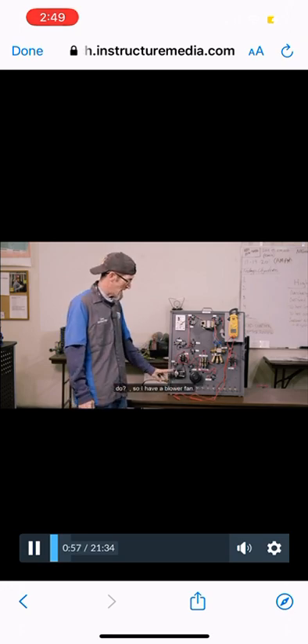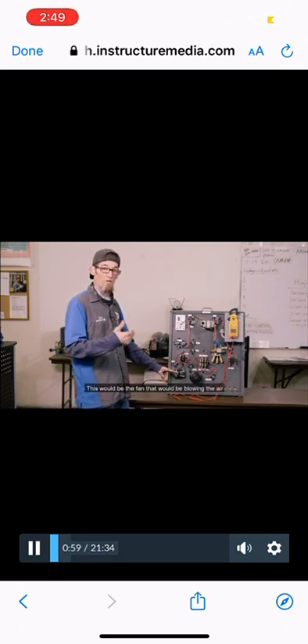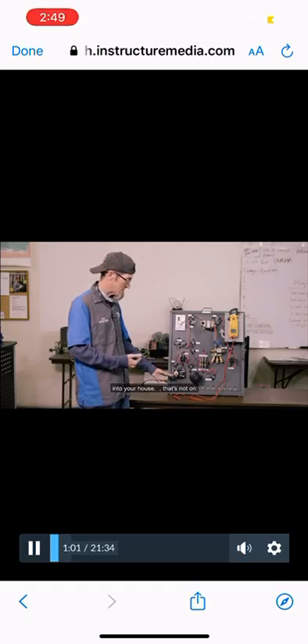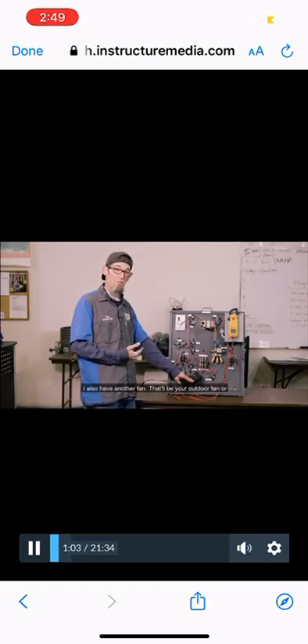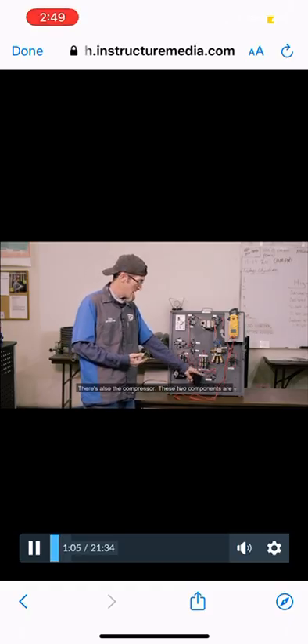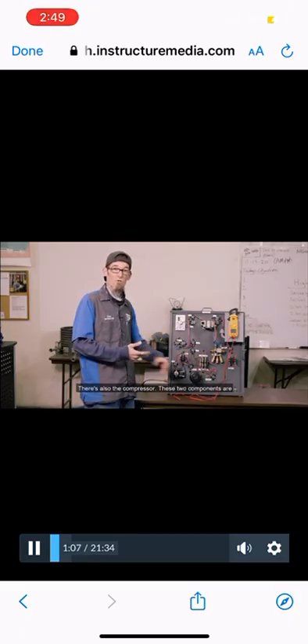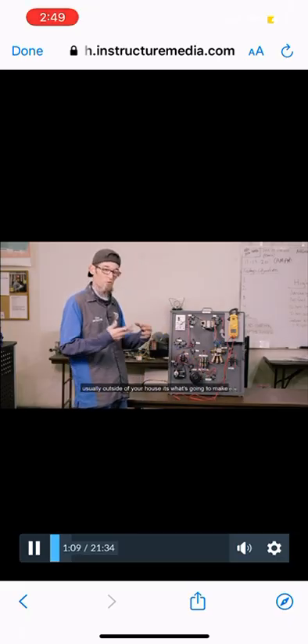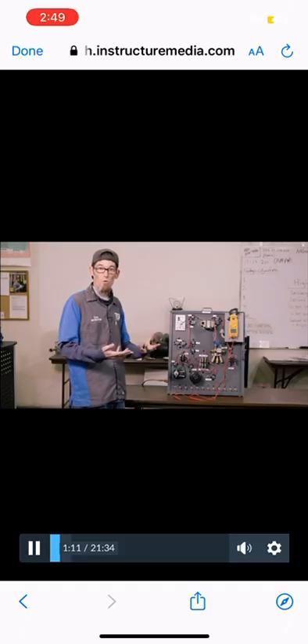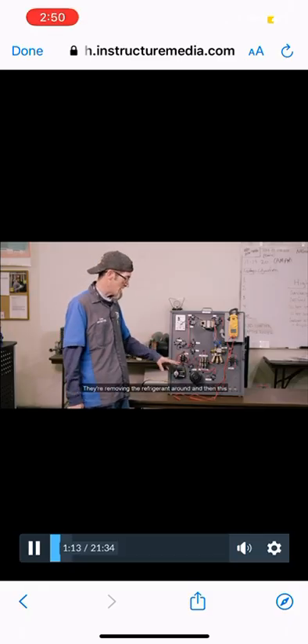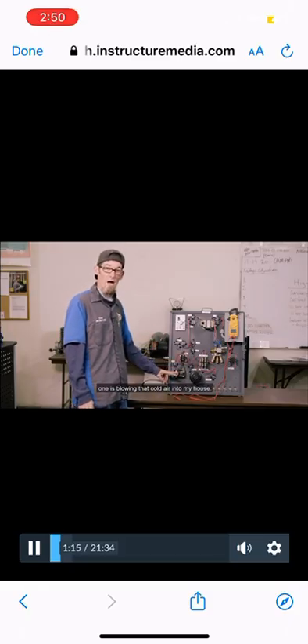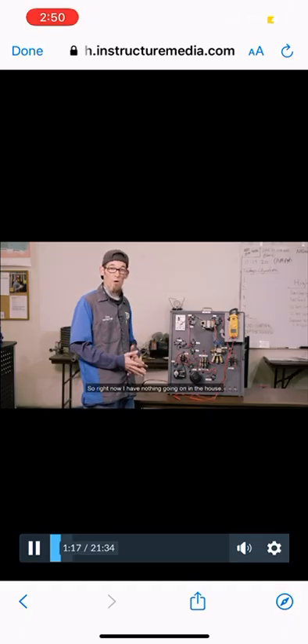Okay, so I have a blower fan. This would be the fan that would be blowing the air into your house. That's not on. I also have another fan that'd be your outdoor fan or the condenser fan. And there's also the compressor. These two components are usually outside of your house and they are what's going to make your air cold. They're moving the refrigerant around and then this one's blowing that cold air into my house. So right now I have nothing going on in the house.